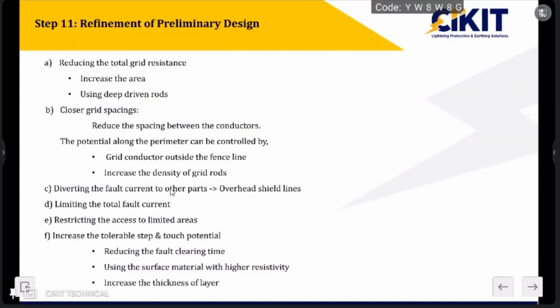The standard has also provided a few points for reducing the step and touch voltages within the tolerable limit. The points provided by the standard for modifying the design: the first one is reducing the total grid resistance. The main problem is because of the GPR. Because of the GPR only, the step and touch voltages are coming into the picture. GPR is nothing but Ig into Rg. So if I reduce this Rg, then the value of GPR can be reduced. That is the reason the first point they have mentioned is reducing the total grid resistance.